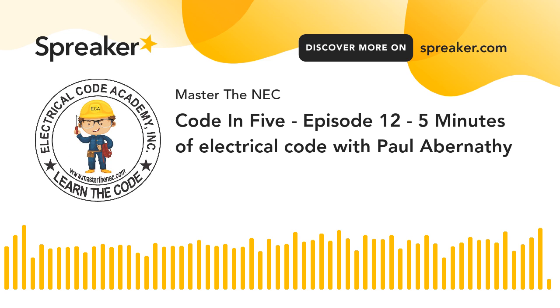Number 6 says that I can use it for non-power limited fire alarm circuits as long as it's consistent with 760.49. So that's another use of tray cable. It also allows me to use it between a cable tray and utilization equipment. So I'm going from the cable tray and extending down to the piece of equipment. Although you have some allowances to support, and you have an exception if it's not more than 6 feet, there are different rules in there. There's A, B, C, D, E, and F that you have to follow, but there is an exception that you can apply if it's applicable to your installation.